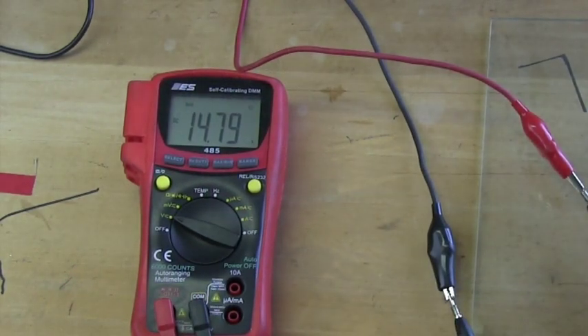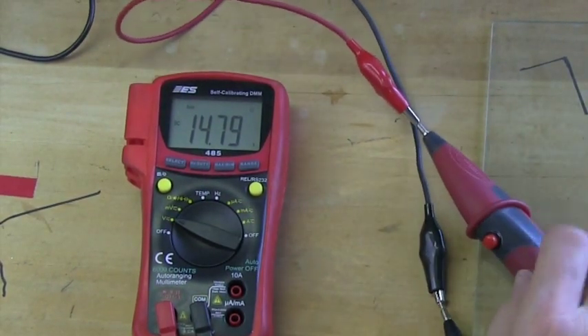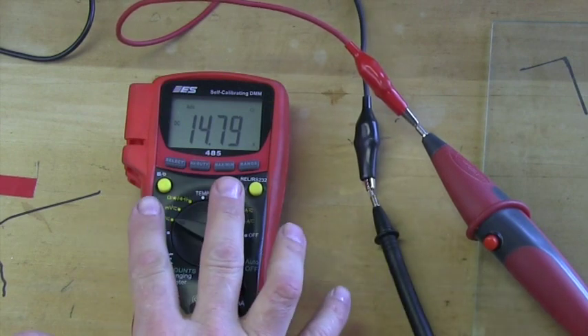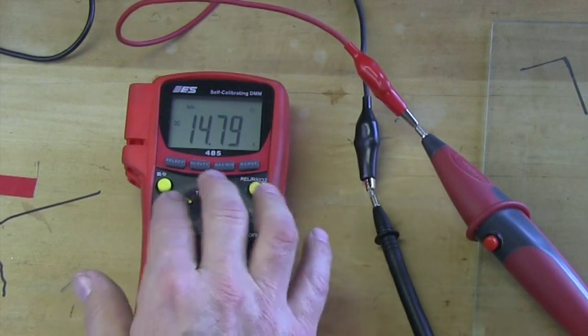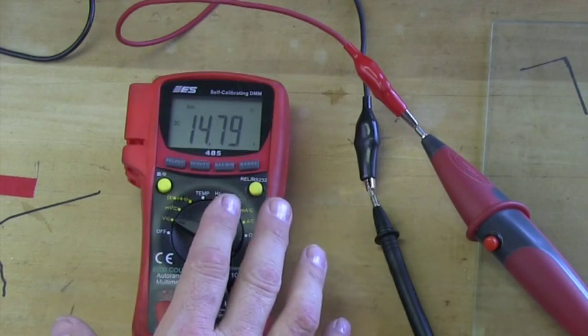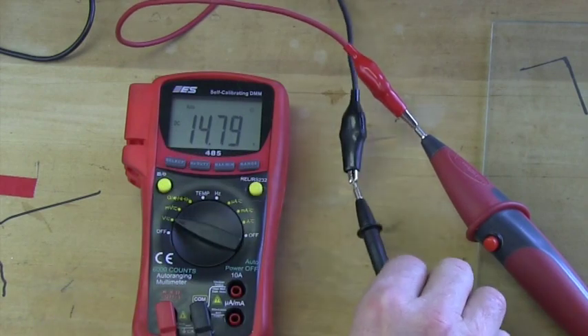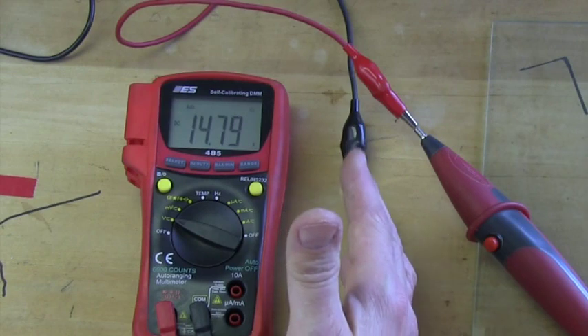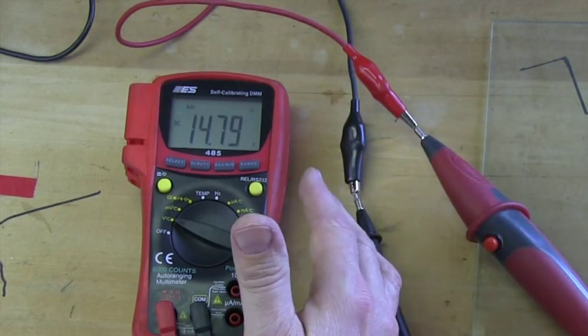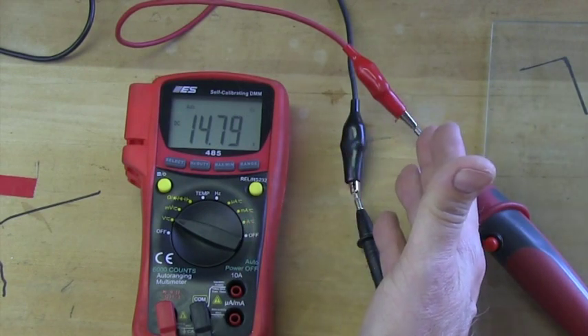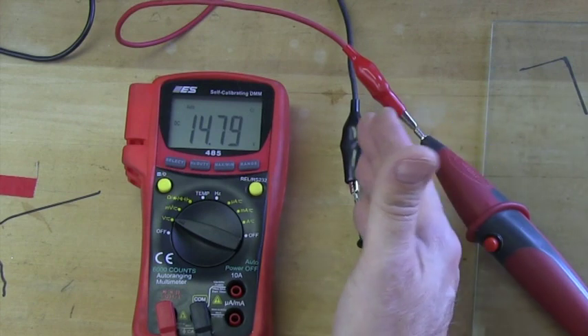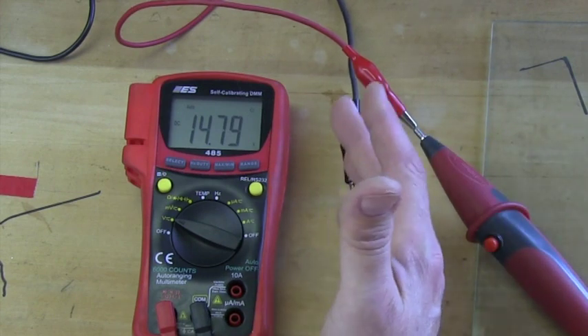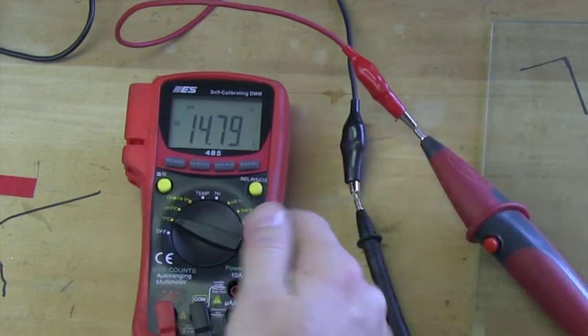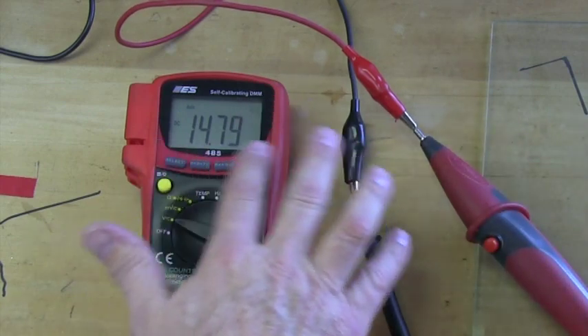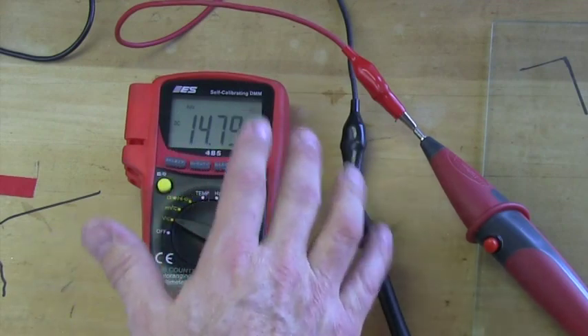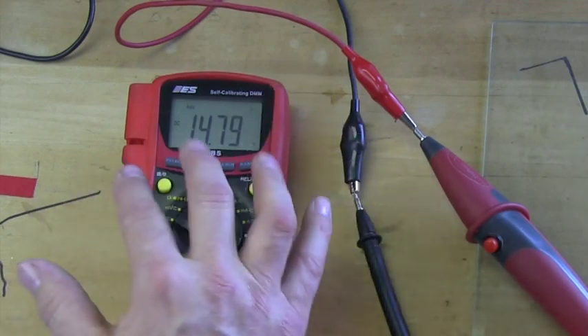Okay, now when you're reading voltage, it's important to understand that the voltmeter is a pressure gauge. So it's going to read the pressure relative to ground. So if you put the black lead on ground, then we assume the ground is 0. So whatever the number we read, we're reading the pressure relative to the ground. Okay, so ground will be 0, and then 14.79 volts. That's not 14 and it's not 15, it's 14.79. Okay, do not round up, do not round down.